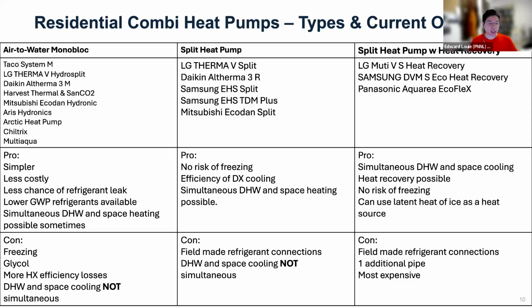So this is a table that is not necessarily an exhaustive list of every product on the market, but it's pretty close to exhaustive. It's every one that I know of. And they're categorized by the different styles of combi heat pump, and you'll understand in later slides why they're categorized this way. There are monoblock style heat pumps, where there's an air-to-water heat exchanger in the outdoor unit, and then it's water or glycol that goes inside the building.